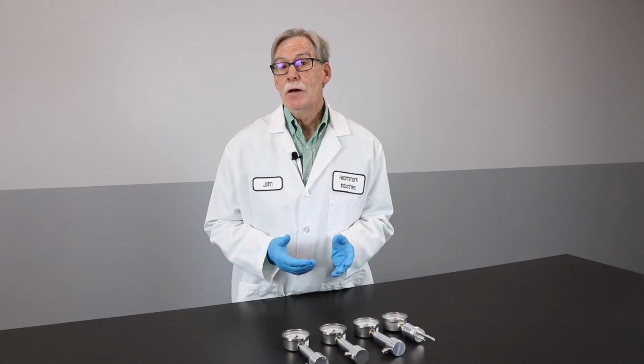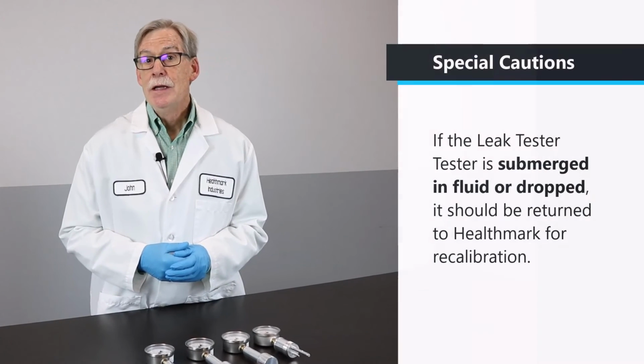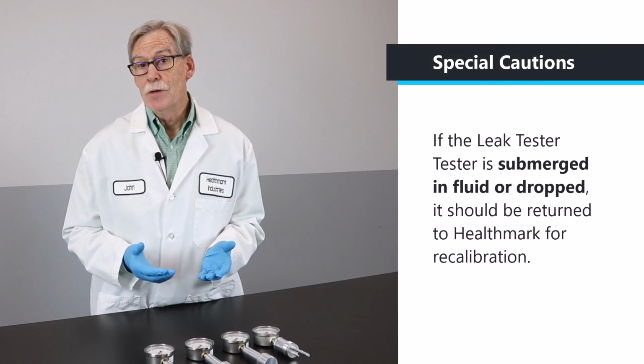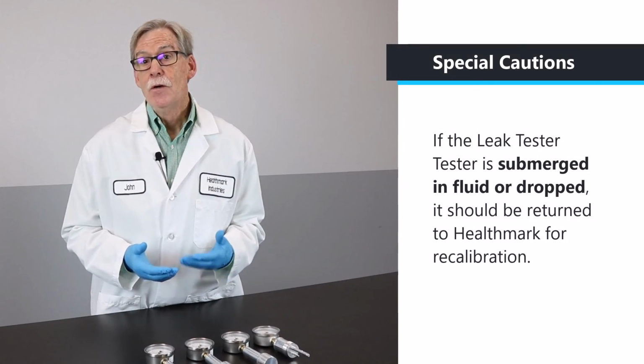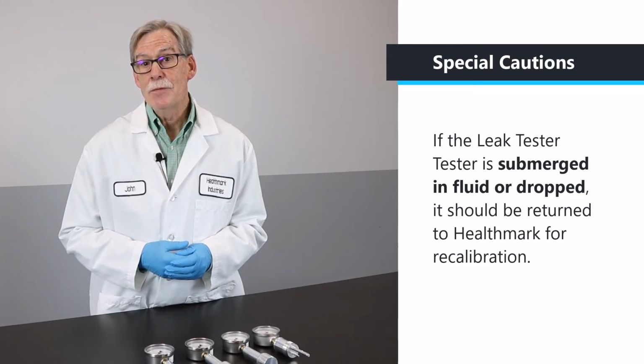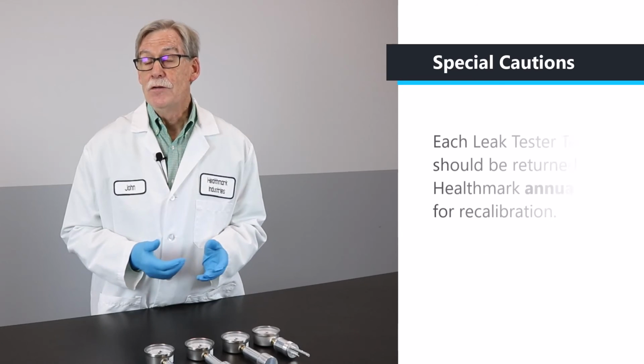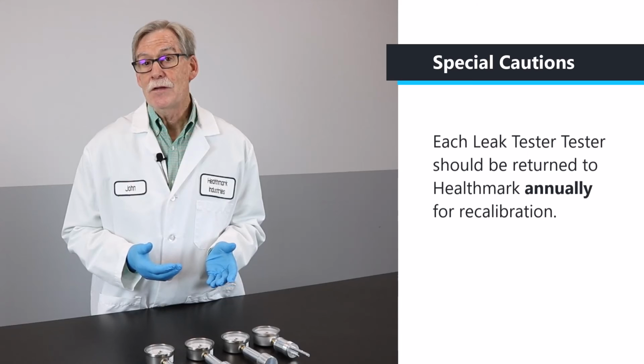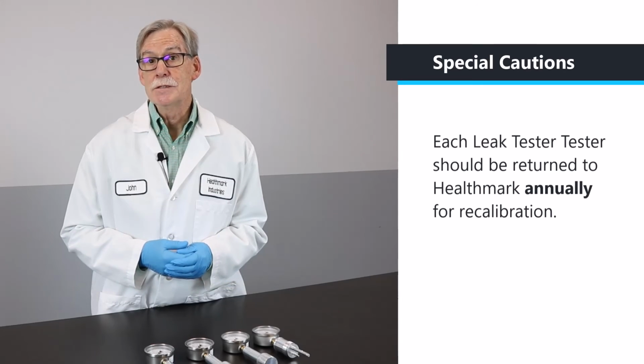I want to just call out a few special warnings and cautions when using the leak tester. If the gauge becomes inadvertently submerged in fluid or the leak tester is dropped, it should be returned to Healthmark for proper calibration. Submerging, dropping, or mishandling the leak tester may damage the accuracy of the gauge. Additionally, each of these leak testers should be returned annually to Healthmark for recalibration.